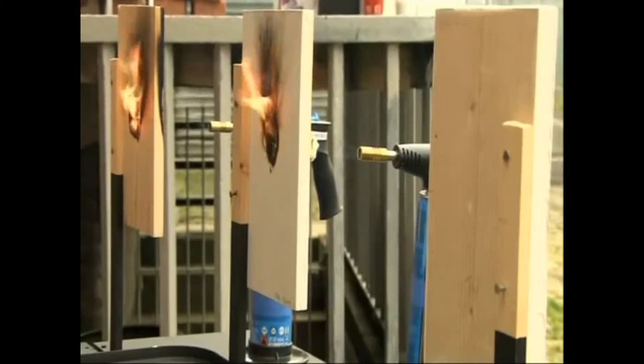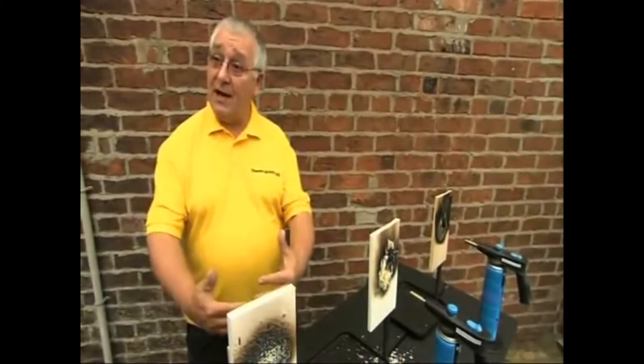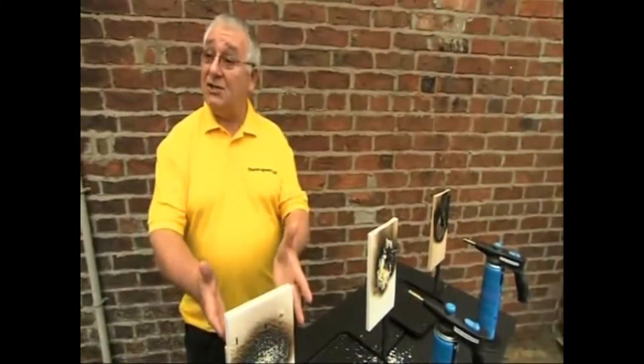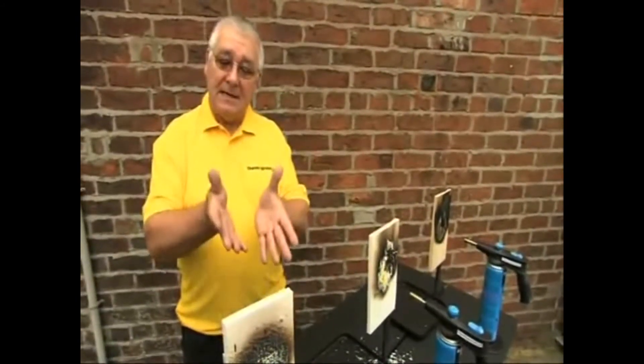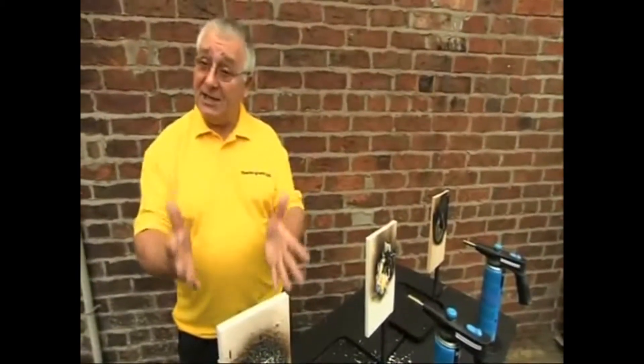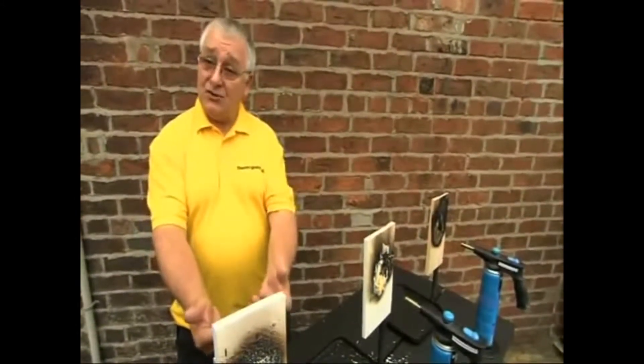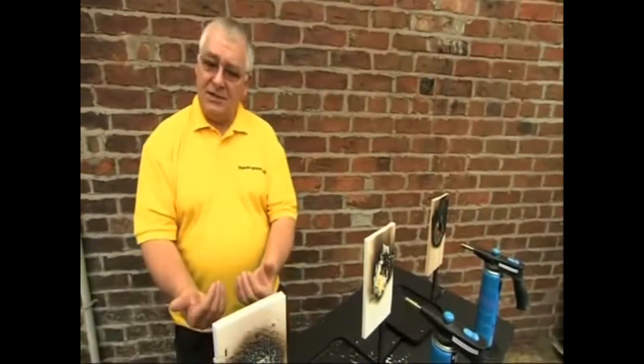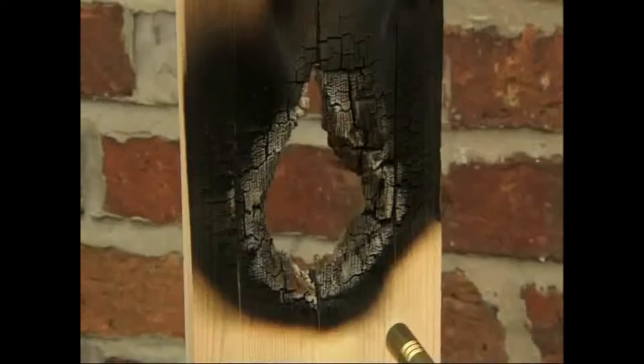What is happening at the back is that there is moisture being released from the wood. The wood is drying out because there is a heat source on the other side. However, the intumescent coating is insulating the wood itself and preventing any transgression of heat through to the substrate, and consequently not allowing it to burn.